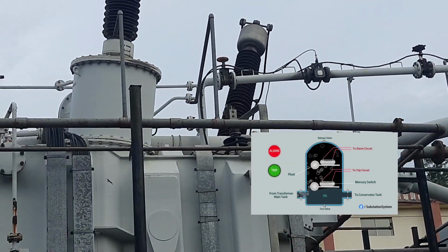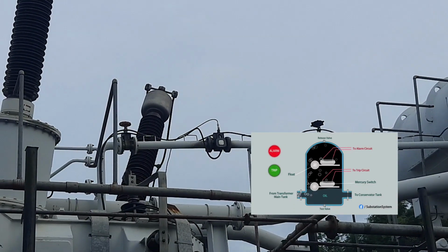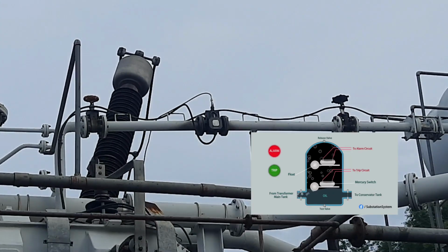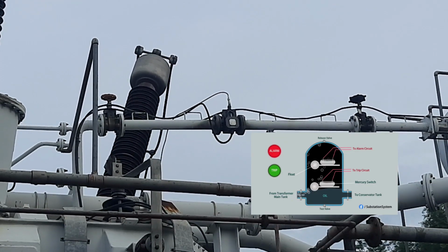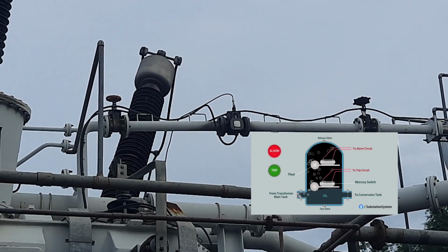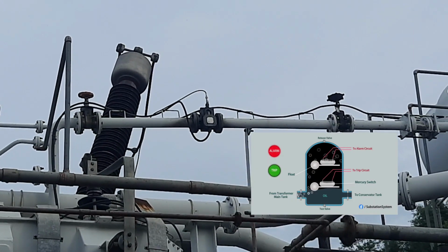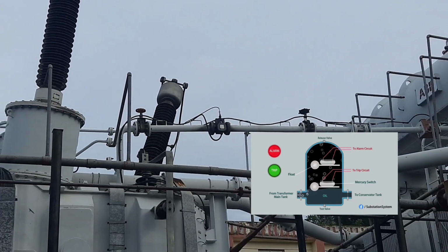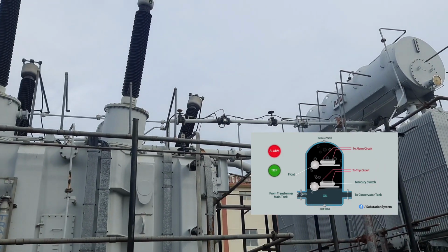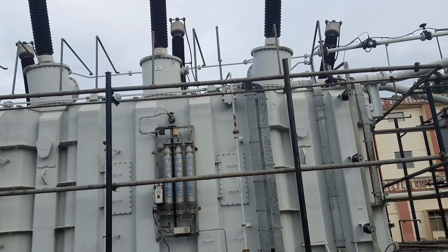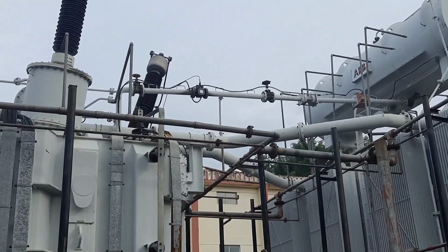The rise of the gas will replace the oil there, and the float device installed inside this Buchholz relay will move down, and because of that, the contacts will be shorted. I think it's a magnetic contact installed in there, because normally we don't use mercury contacts in big transformers. With a mercury contact, if there is an earthquake, you may get false tripping that will affect the power flow, because the rating of this is huge, so it will affect the power flow in any region. So that's why we are using this magnetic contact.